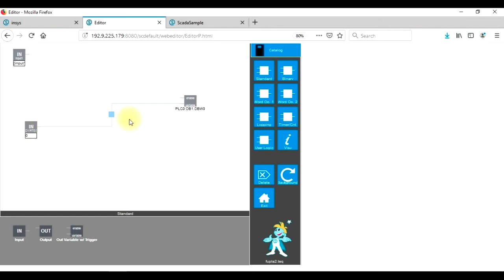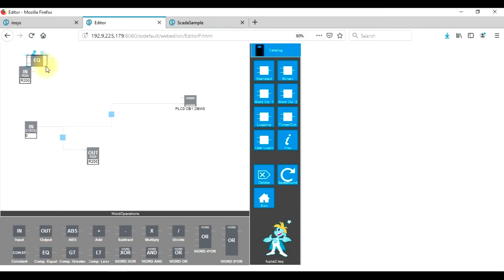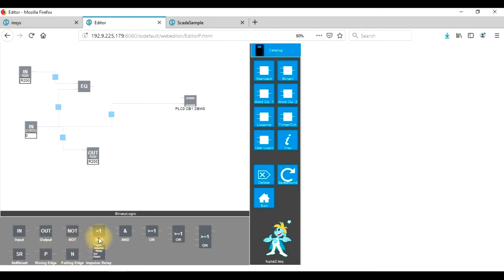Now, because we don't want to constantly copy the input value to the output value, we will implement a simple trigger logic which compares the current status with a saved status. To do so, we'll copy this input value to an internal register called R200, for instance. We'll take this register again as an input, R200, and make a compare of the register and the current value. We will invert this and create a trigger on the rising edge. So this is how this should do the trick.